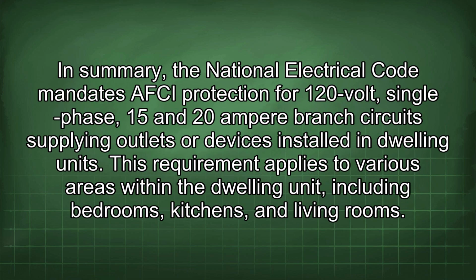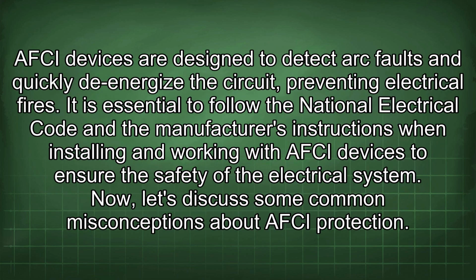protection. In summary, the National Electrical Code mandates AFCI protection for 120-volt single-phase, 15 and 20 ampere branch circuit supplying outlets or devices installed in dwelling units. This requirement applies to various areas within the dwelling unit, including bedrooms, kitchens, and living rooms. AFCI devices are designed to detect arc faults and quickly de-energize the circuit, preventing electrical fires. It is essential to follow the National Electrical Code and the manufacturer's instructions when installing and working with AFCI devices to ensure the safety of the electrical system.